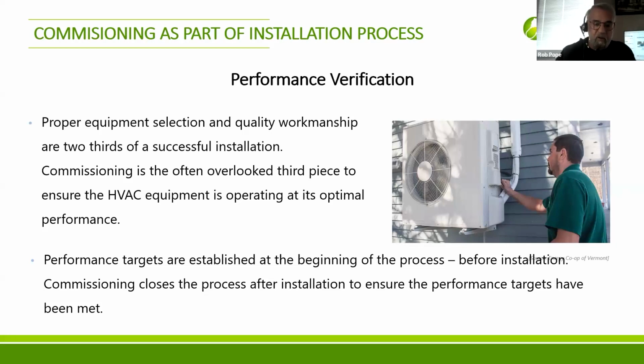As I said, it's often overlooked. Typically, worst case scenario—and it's not dire straits out there all the time, don't get me wrong—but too often what happens is the installation is completed, you fire it up, turn it on, if it's summer you put it into cooling mode, and you check the registers with your hand. Okay, air's coming out, it's cool, is it achieving the set points? Great, pack up, clean up, and leave. A variation of that happens far too often, when there are a lot of things, as we'll see later on, that you really need to do.